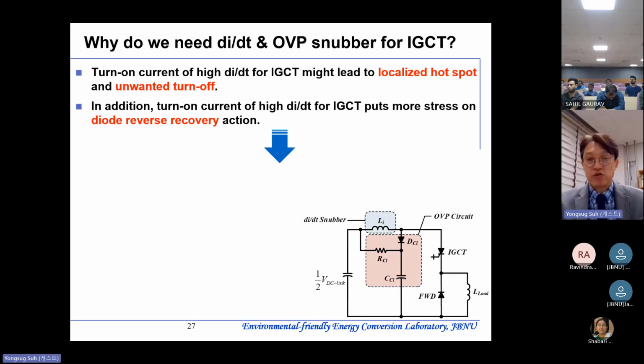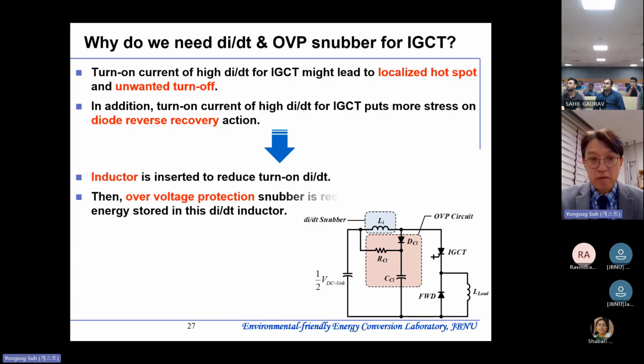So this is the usual way of limiting the DIDT. Here is the DIDT snubber, and when you turn off, we need to bypass the energy stored in it. This is called an RCD snubber, which everybody knows well. The power rating for one IGCT is a few kilowatts, so we're talking about a few kilowatts of power loss, and this resistor is water cooled - it's called a submarine resistor. Price-wise it's very bad, and volume-wise it covers significant space in the medium voltage drive cabinet.